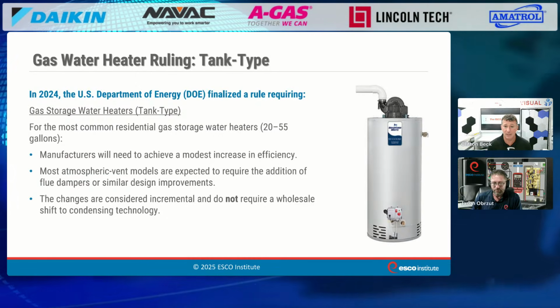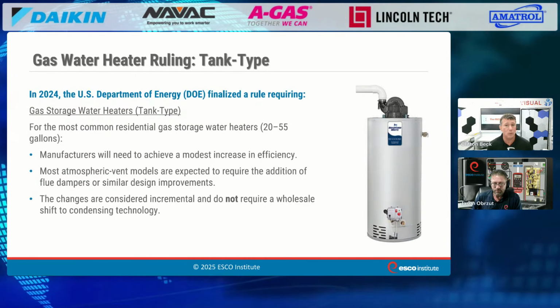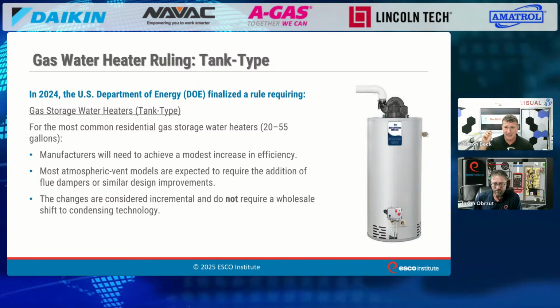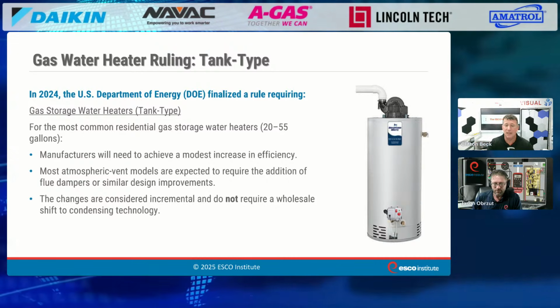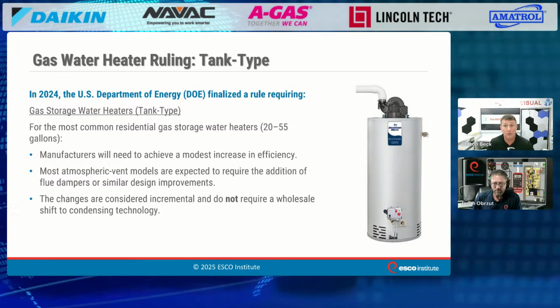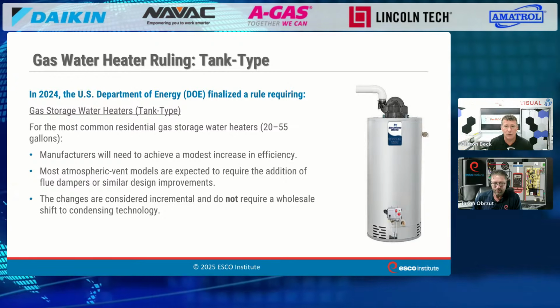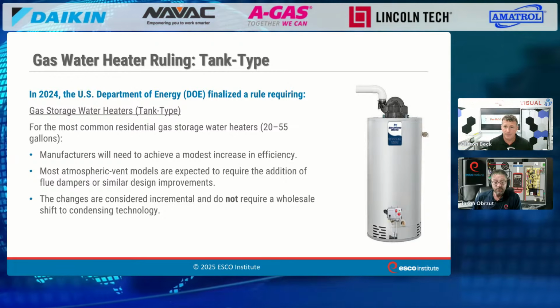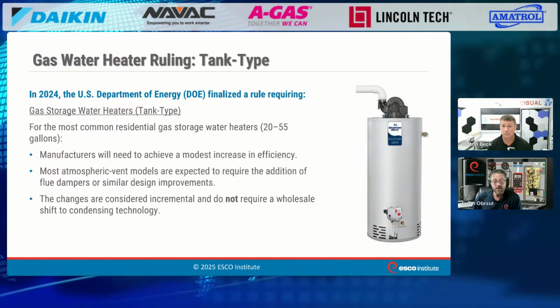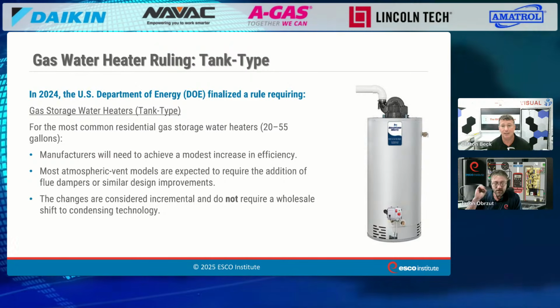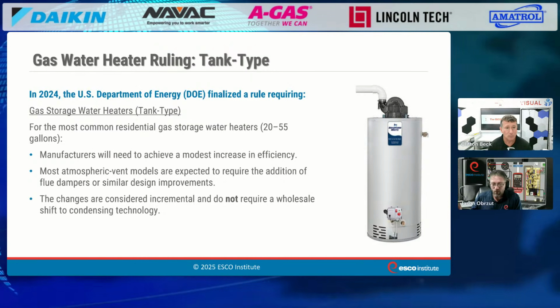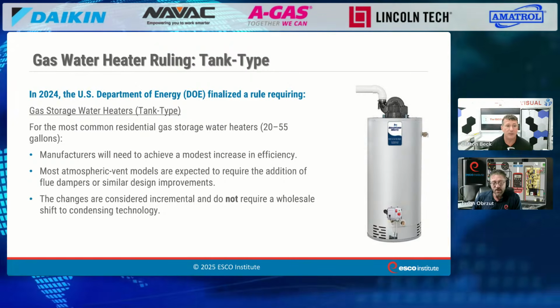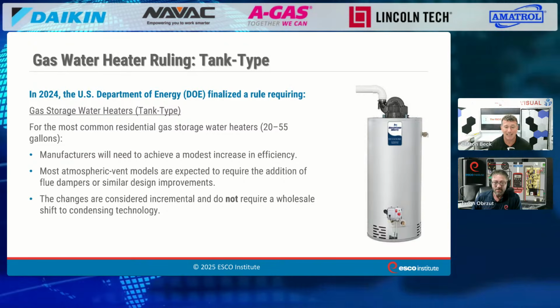But what we can do, as we've already seen, is go to a power vent style and not have to go into condensing. We increase efficiency without passing the condensing temperature of the flue gases, which would require secondary draining and exchanging—that's a big deal, because venting on a condensing unit can't tie into a chimney or any other vent. It has to be its own dedicated vent, meaning you have to drill a hole in the side of the building, and that becomes a big problem.